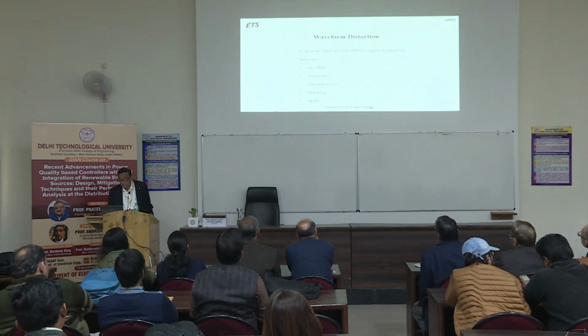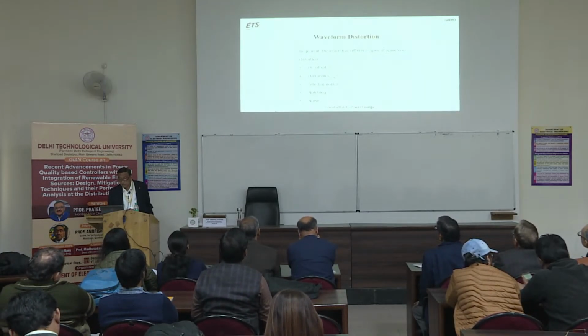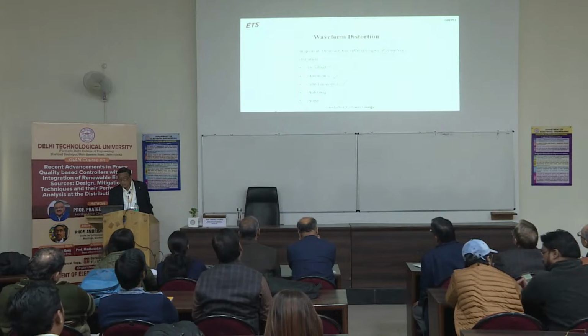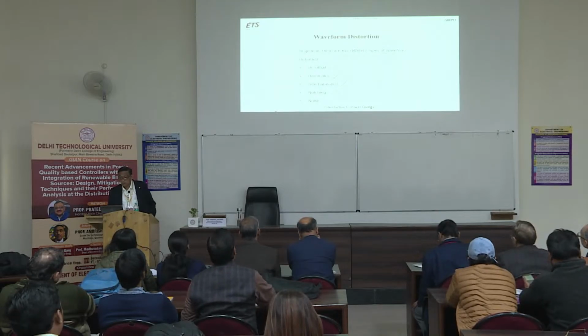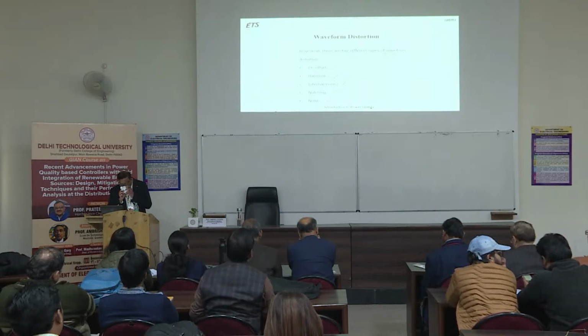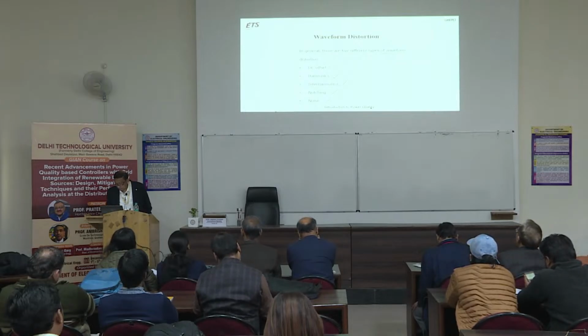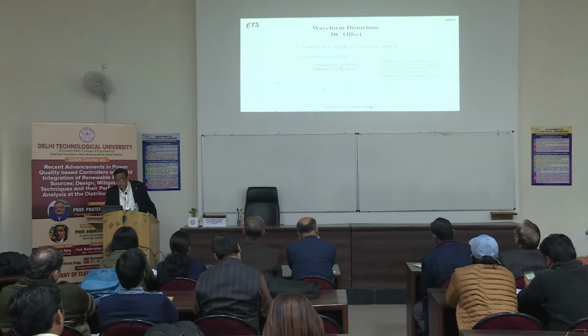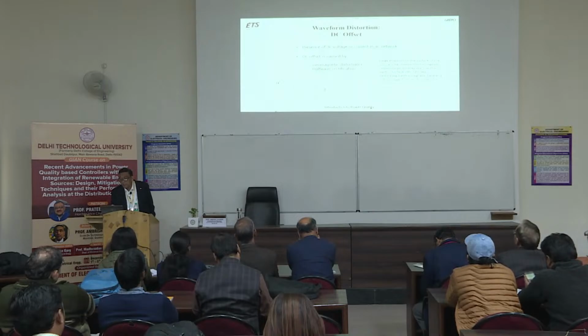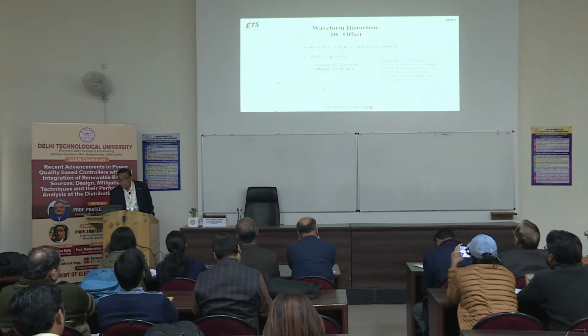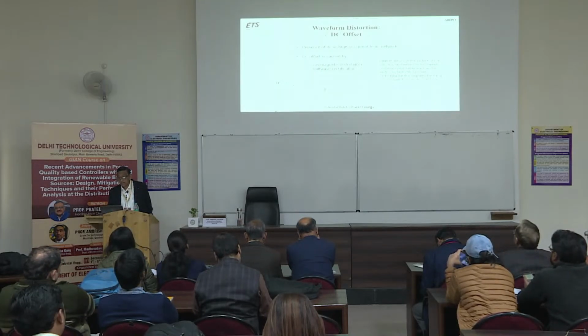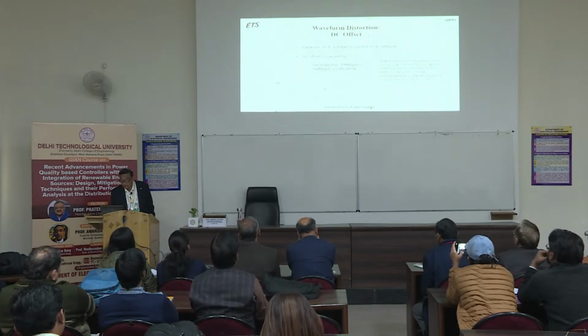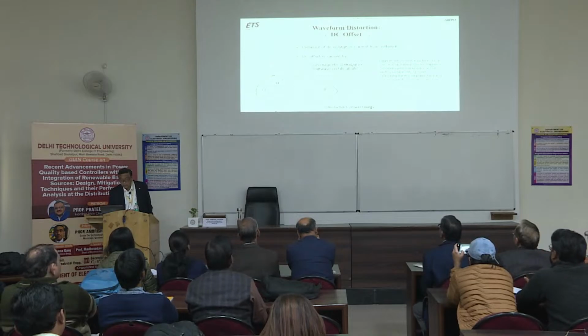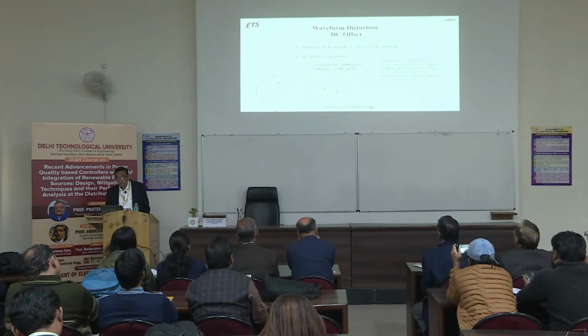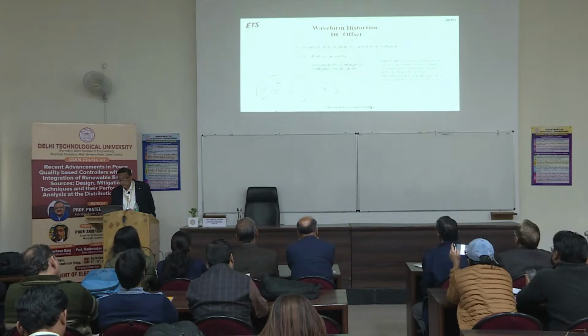There may be DC offset, harmonics, interharmonics, notching, and noise. Those are the five types of waveform distortion. Now, DC offset is the presence of DC voltage or current in an AC network. DC offset is caused by half wave rectification. You already know the half wave for single phase or three phase, so this may cause DC offset.